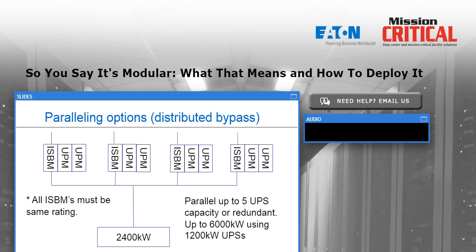I don't necessarily have to pull a neutral wire over to my paralleled UPSs. I can treat it from that point as a three-wire system. But it's more common to parallel three-wire to three-wire, but most vendors can also parallel four-wire to four-wire. And if I'm talking about, for example, a smaller system that's rated at 208, 120 volts, then, of course, in order to support the critical load 120-volt devices, I would have to have a four-wire UPS system, and it may be part of a parallel system. No problem there.